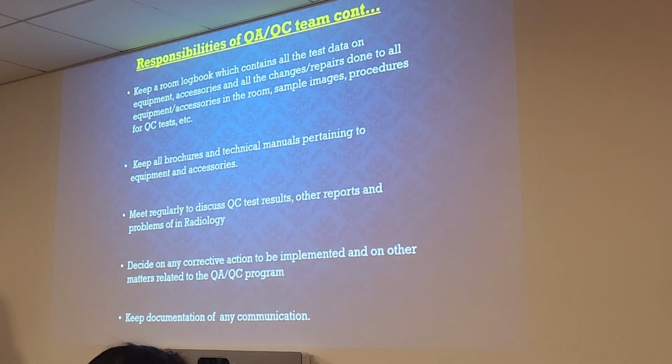And communication being, say, if the x-ray room goes down on first shift, it's the responsibility of the lead tech or whoever discovers that the room is no longer working. They put in a trouble ticket to Biomed to let the next shift know what's going on, which is called the hands-off approach.